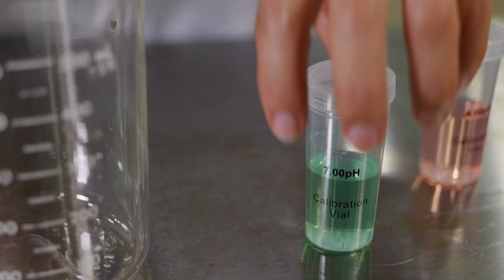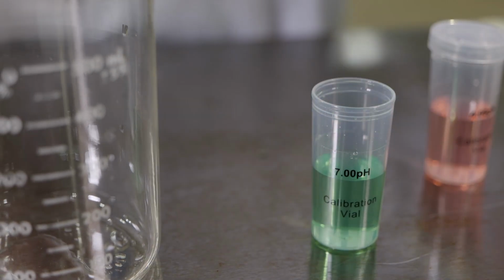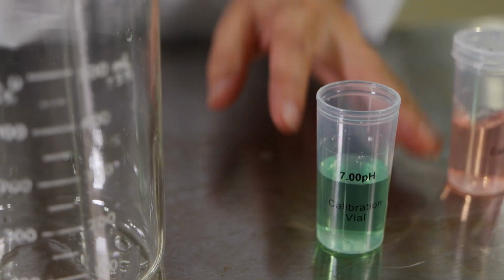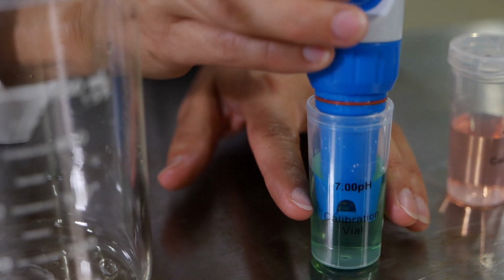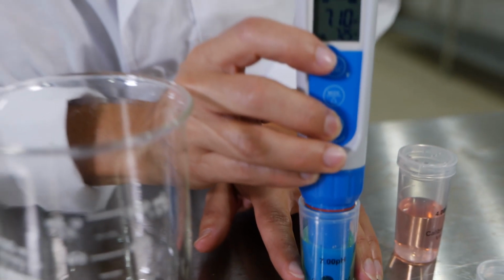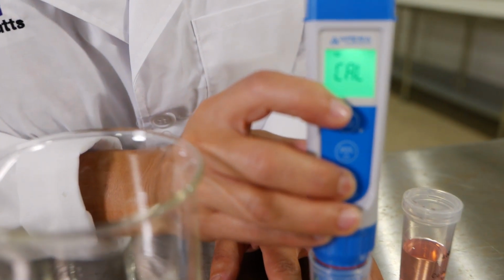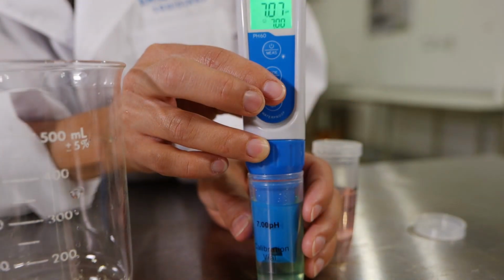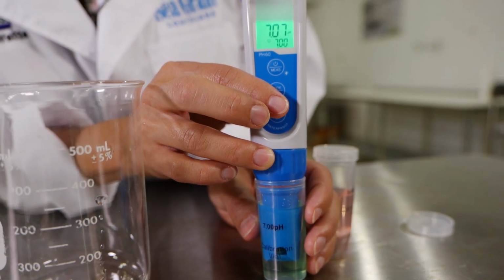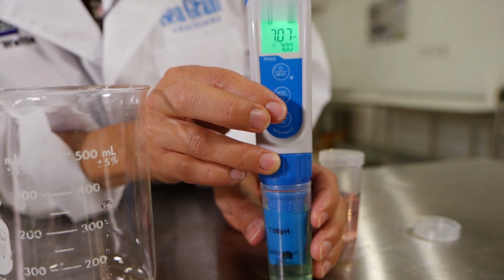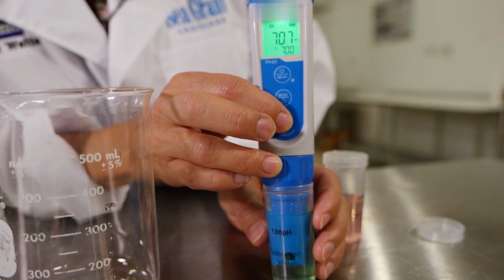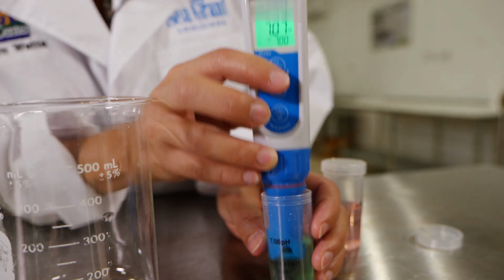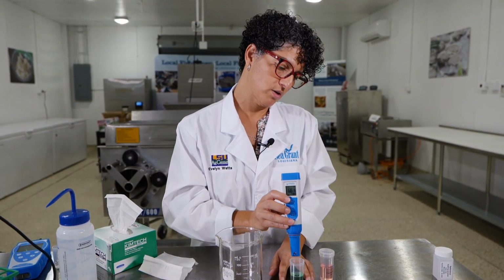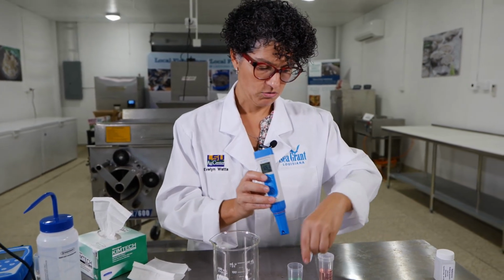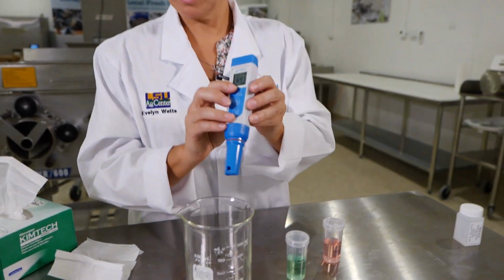For our first calibration step, we're going to go to our pH 7 solution. We're going to immerse the probe, and we're going to hold the calibration button, and then we're going to let the pH meter do its thing. In this case, this pH meter shows a smiley face when it's done, so we can press again the calibration button. Between calibration solutions, you do want to rinse your probe to make sure that it's properly clean.